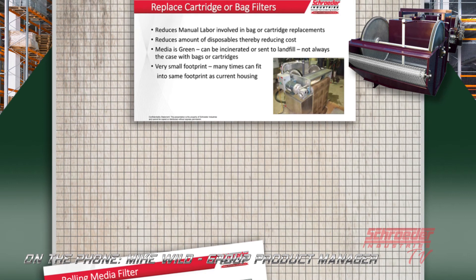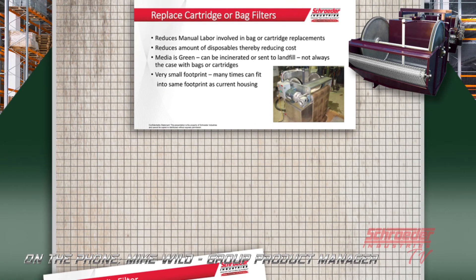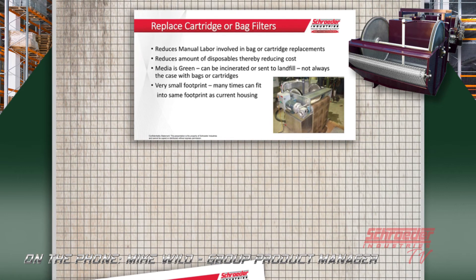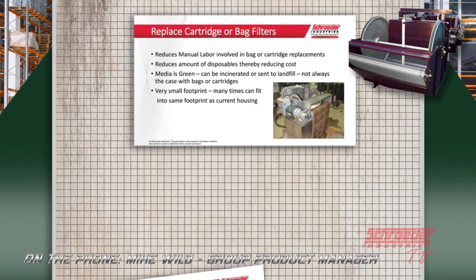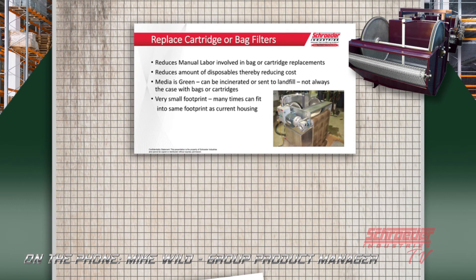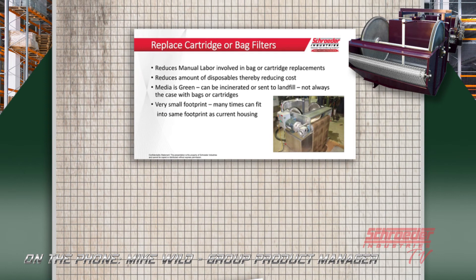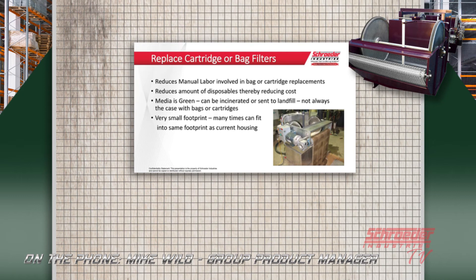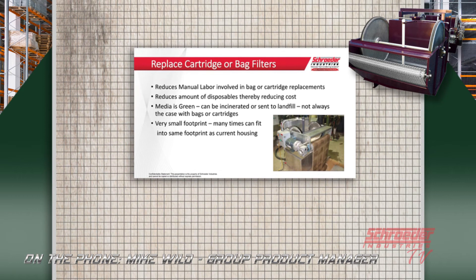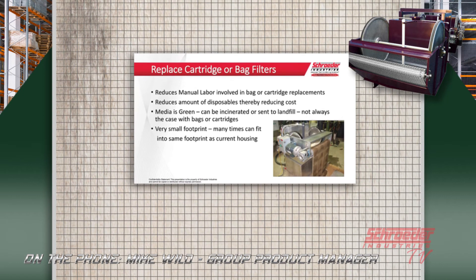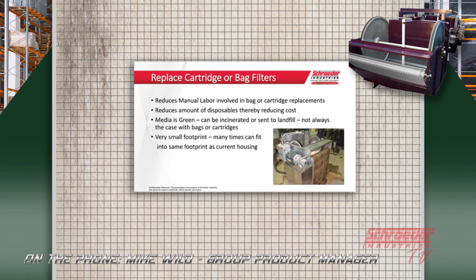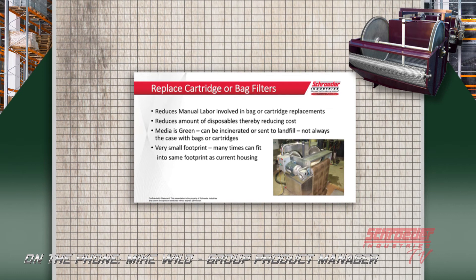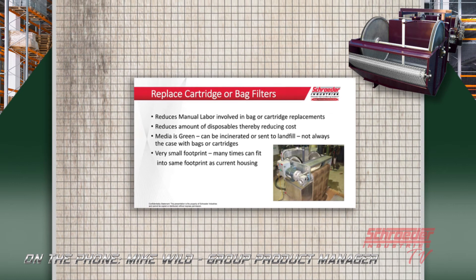Another good application is replacing cartridge or bag filters. If your customer has multiple cartridges or bag filters, they're spending a lot of time and manual labor removing those bags and cartridges. The rolling media filter can be a good replacement to reduce that manual labor and also reduce the amount of disposables they're currently paying for. It also has a very small footprint — it could go into the same area as the bags or cartridges already. The media is also green: it can be incinerated or sent to the landfill, which isn't always the case with bags or cartridges.